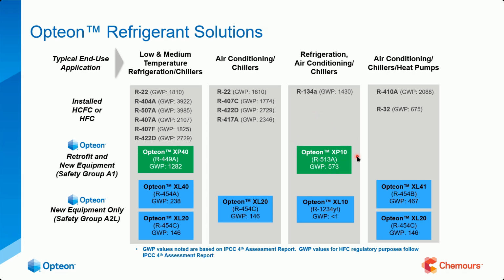Over here, we're looking at the replacement for 134A, typically found in medium temp applications and also air conditioners. Okay. The GWP is 1430, 1430. So a great replacement for 134A, probably the best retrofit gas most people have ever seen, is R513A. GWP is 573. You literally don't have to change anything.